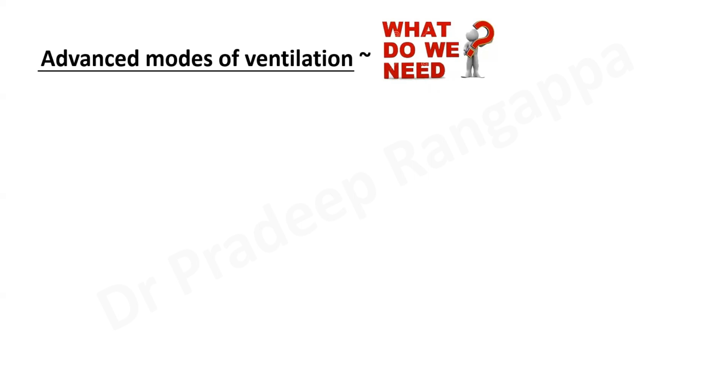You don't have to worry about what sort of volume assist you should give, what sort of preset pressure you should give, and what tidal volume is good enough so that I control the pressures, or what amount of pressure I should preset to ensure that tidal volumes are achieved. You don't have to break any heads. You can set the tidal volume and even define what pressures you should limit. Or you can set the pressure and even define what sort of tidal volume you should be achieving. All these are done with advanced modes.